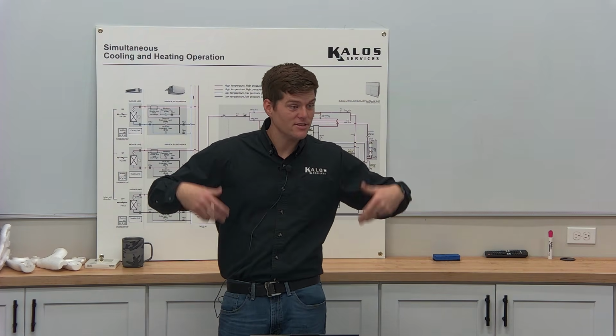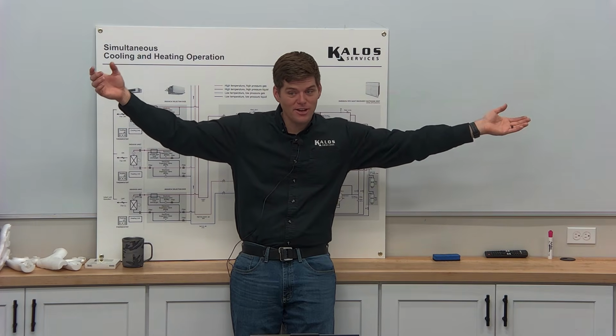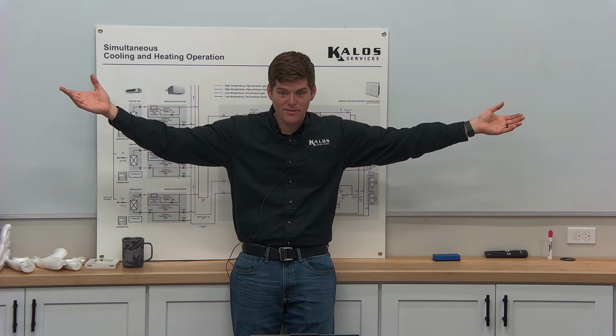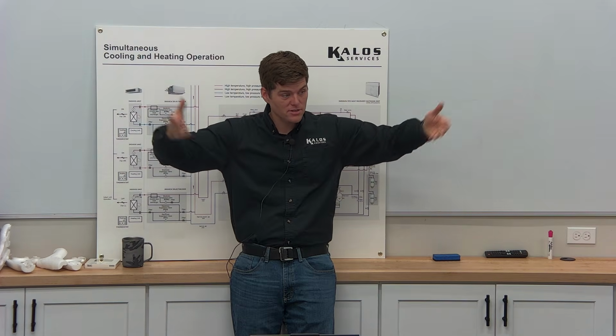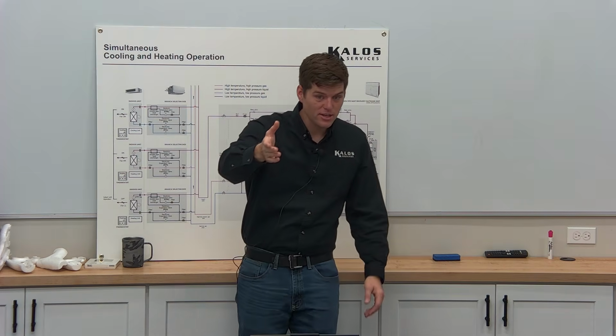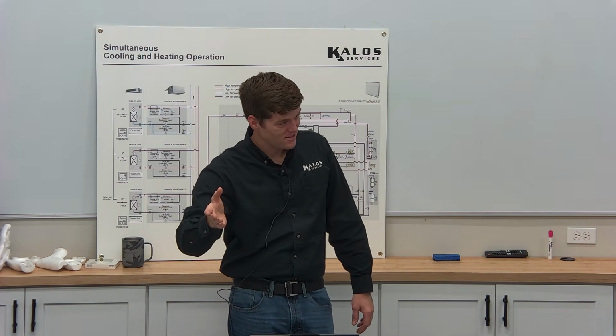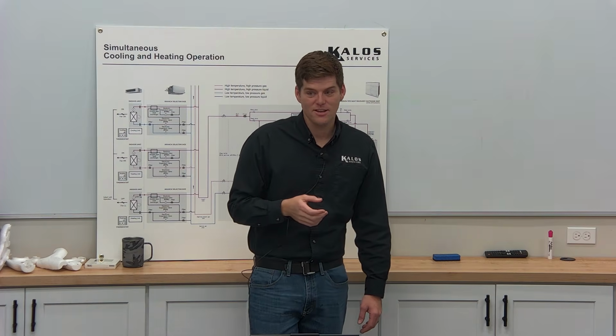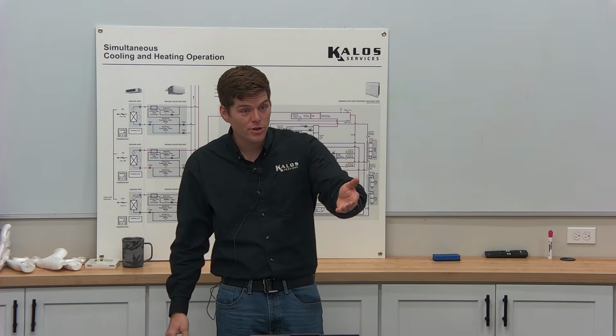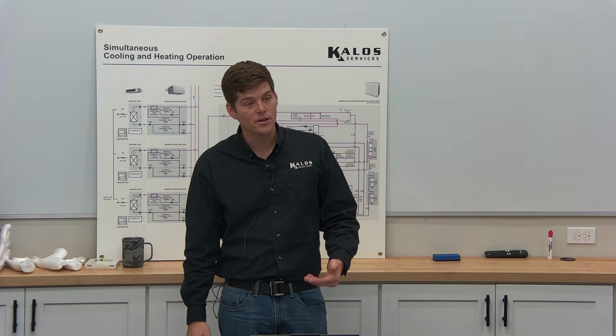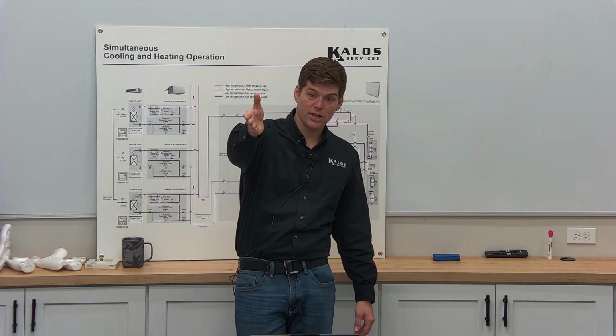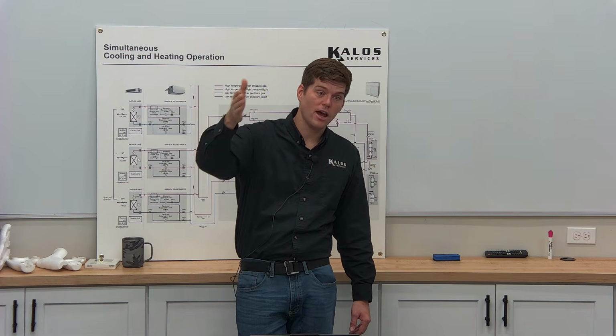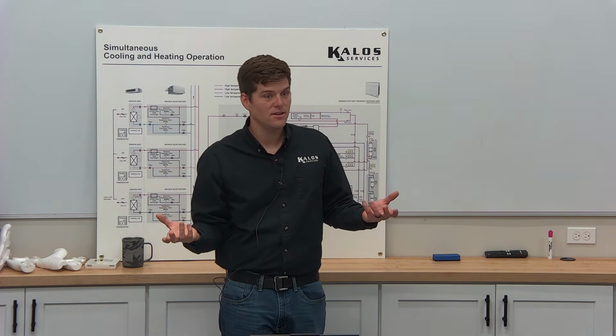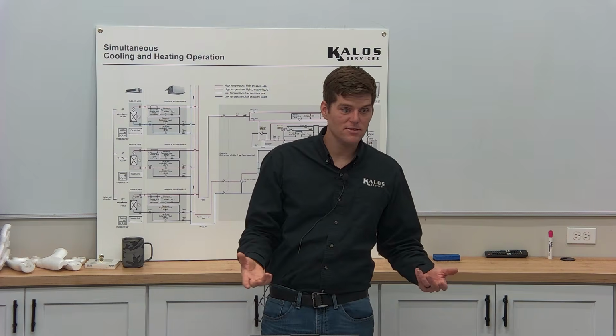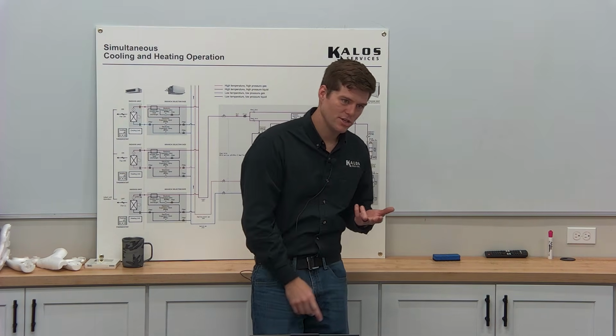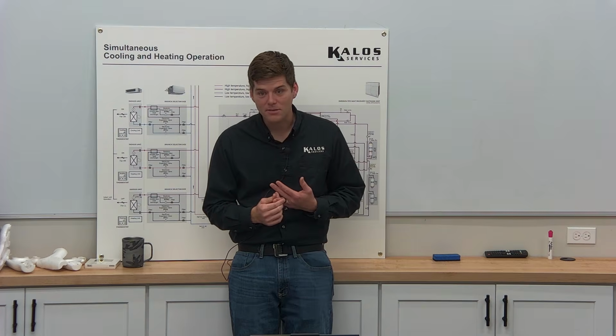We're trying to create less resistance. When you have literally a half-ton all the way to an 8-ton system, you have to have the ability to connect anything to the system. Those are actually reducers and couplings for different size refrigerant lines. So based upon the type of indoor unit and its liquid line size will determine, do I cut it? Do I leave it at the 1/4-inch connection at the tip? Or do I cut it one notch back where it expands to 3/8? Less braze points, less leaks, less contamination, less time.